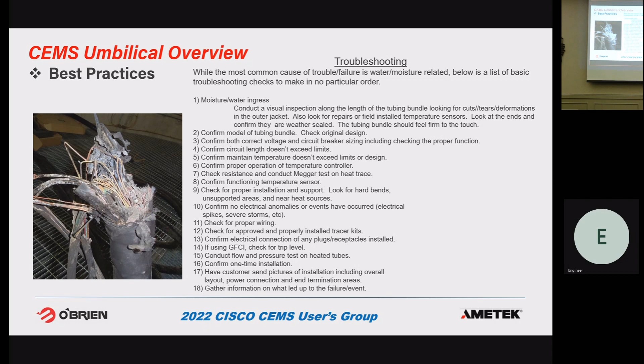After it's installed, here are some things I like to do. You've done your resistance and megger test before install, so let's do that again. Let's also check if there are any temperature sensors, and check those. Go back and check all the weather sealing. Like I said, during install it's not uncommon to cut the jacket.